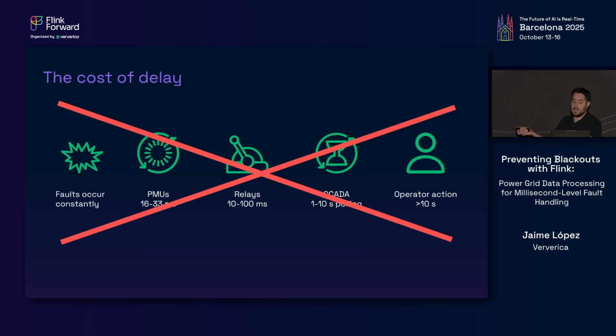When we go back to this, we see that by the time that operation understood what's going on, it was too late. There's nothing they could do. No manual action, no SCADA. So the grid has to be able to react at this scale. And this is basically 1/10 of a human blink. A blink is 250 milliseconds. So in 1/10 of a human blink, I need to detect it, and in half a human blink, I need to act on it. Literally, using a very abused phrase, blink and it's gone.